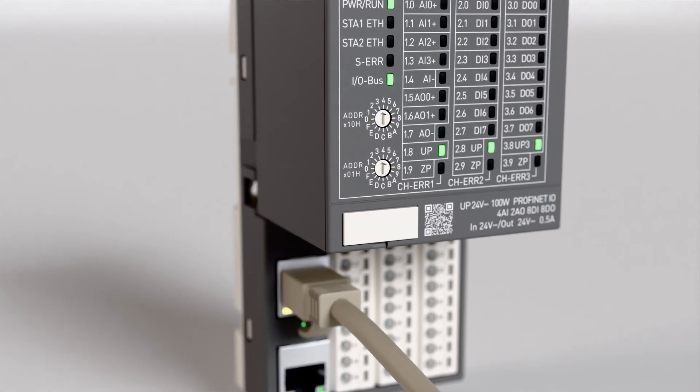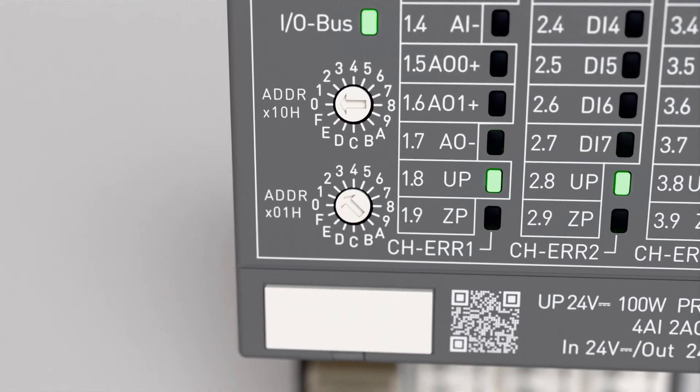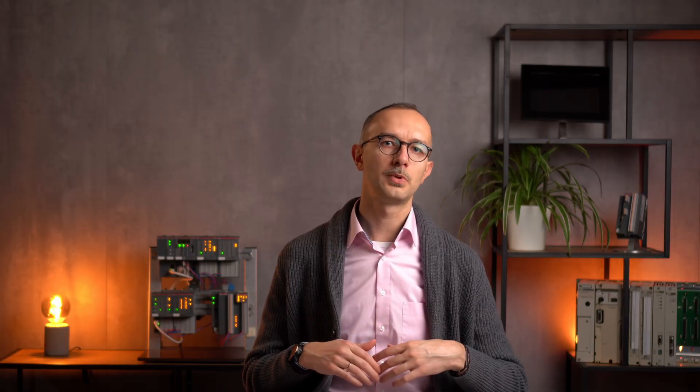Well, in case of CI501 module, there are two ways. First one: device name has two parts, fixed and variable. Fixed part is CI501-PN- and the variable part comes from these two little rotary switches on the front panel of the module. If upper switch is set to 0 and lower switch is set to 1, then station name would be CI501-PN-01. We will talk a bit later about the second way to set a device name.